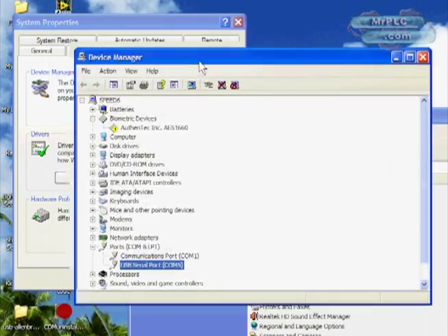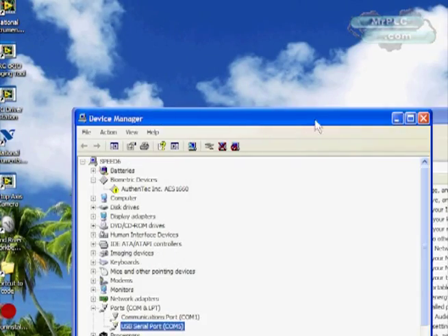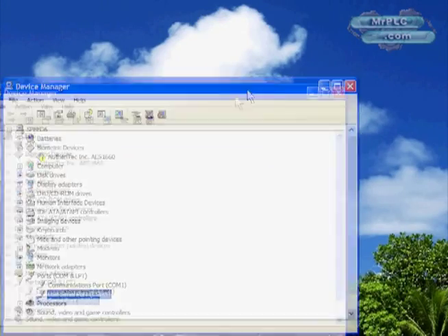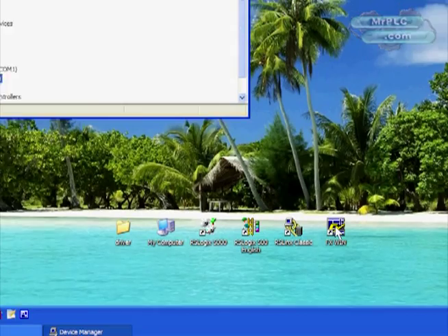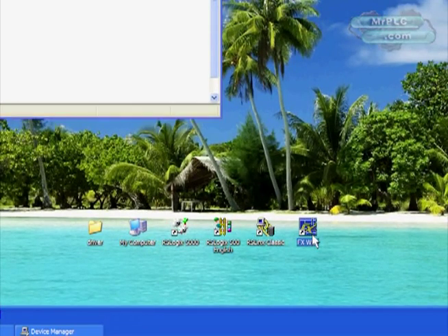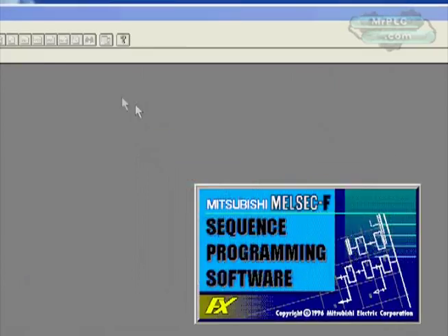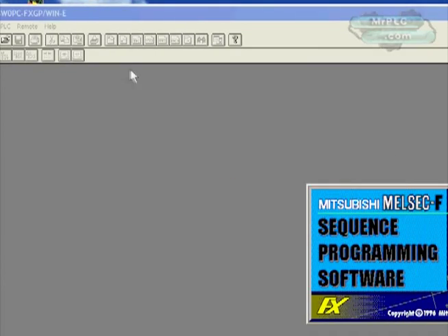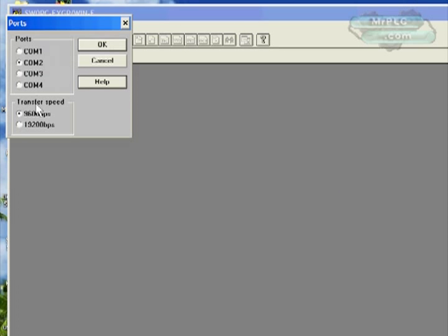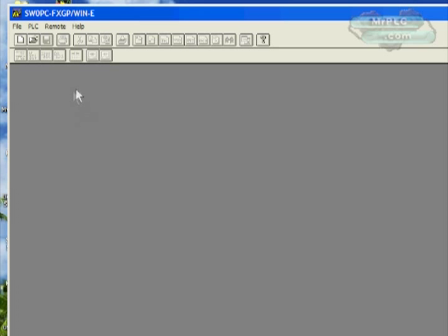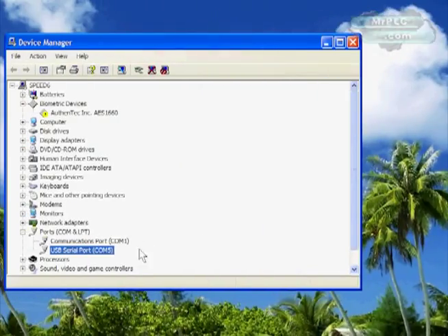Now I'm going to show you something that's actually a problem here with the old software. I'm going to leave device manager right there for now and open up FXWin software. This is an older piece of software to program Mitsubishis with. If I go into PLC ports here, you'll notice there's only the COM port selection 1 through 4. There's no COM5 here. That poses a problem for us right now because Windows has installed the port on COM5 but the software is only compatible to COM4.